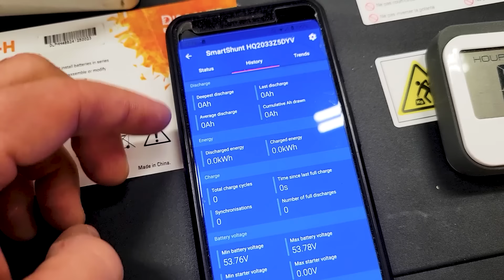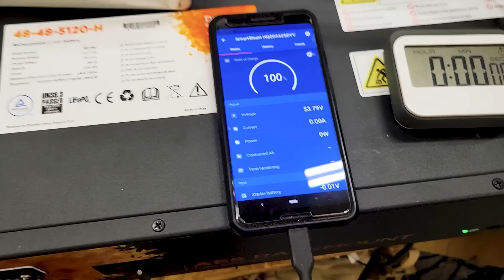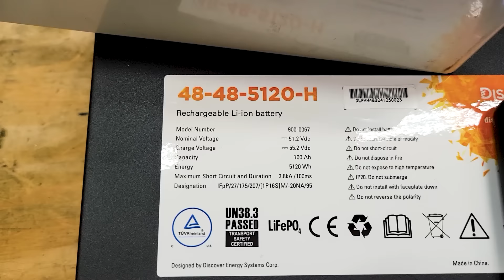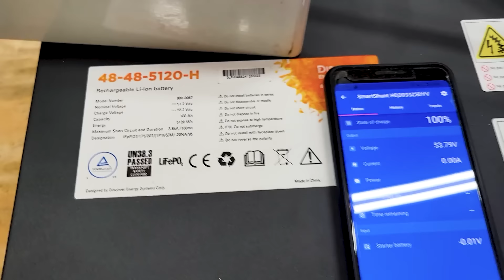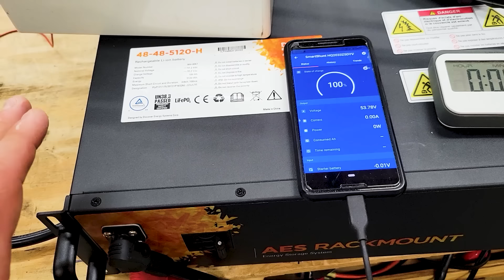All right, we are fully charged and ready for our next test. This will be the capacity test. We're at 100% state of charge, and I zeroed out the history. For the capacity test, we want a C5 rate, meaning 1/5 the total amp hours. This battery is 100 amp hours, so we want 1/5 of that, or 20 amps, which will take 5 hours to discharge. We're going to try to get as close as we can to a constant current of 20 amps.